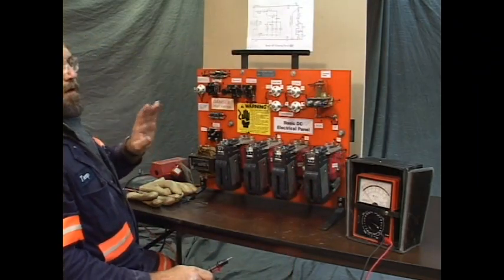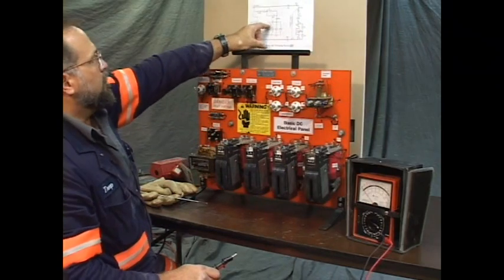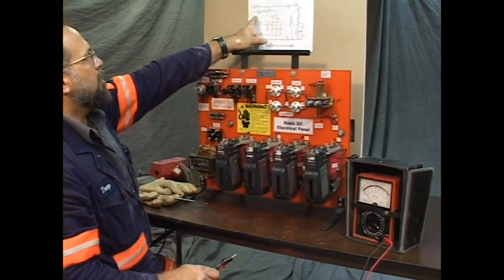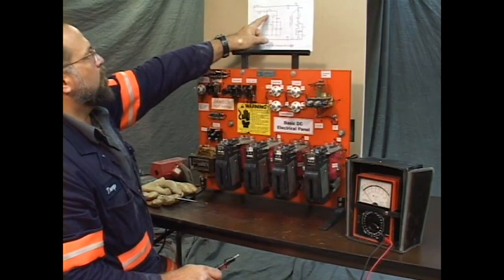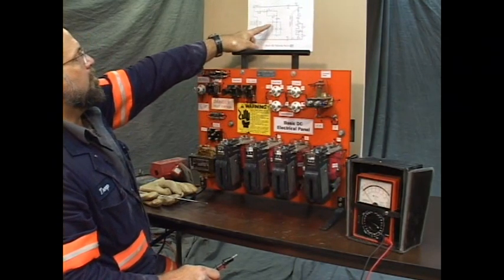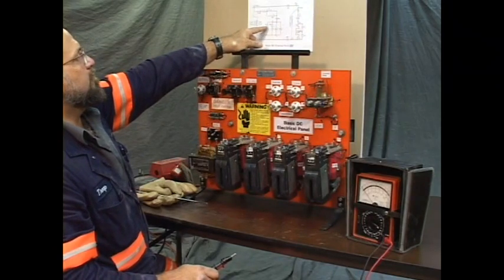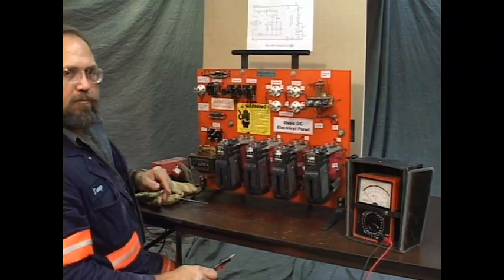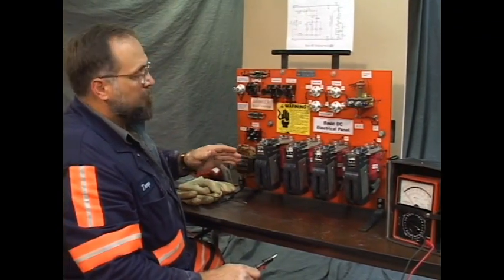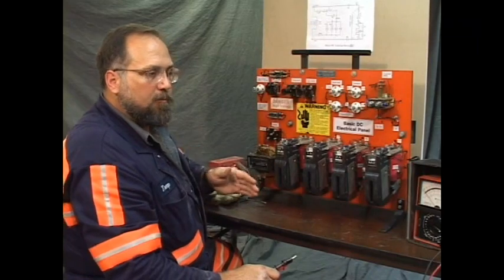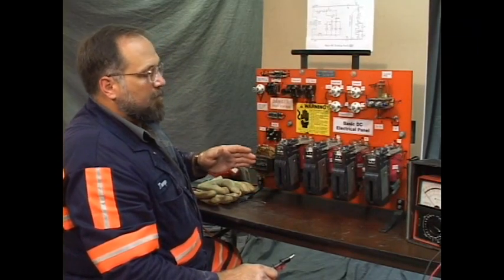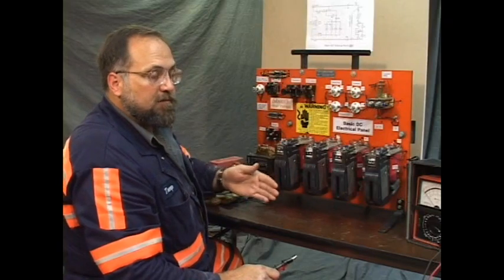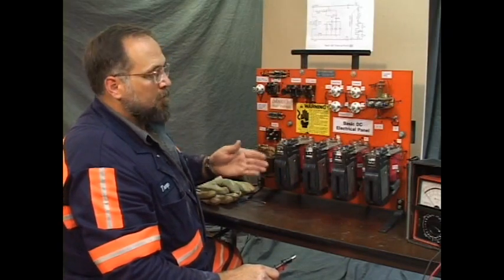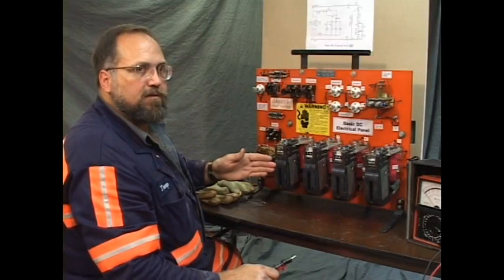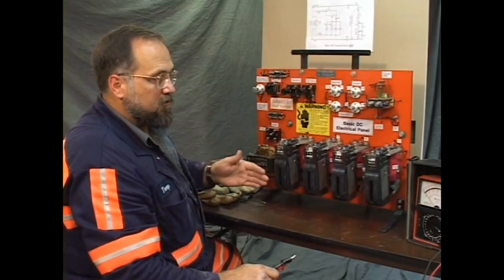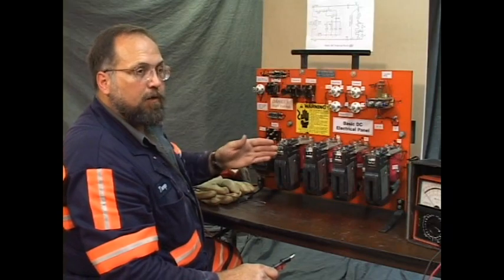Had there been a problem anywhere on that circuit, if you remember the problems that we found, we had an open wire here, we had an open wire here, we had an open wire there, we had a shorted mercury tube, we had a shorted mercury tube. Out of the 15 that we checked, those problems became apparent after we saw the symptom, we read the problem, we saw the panel operate, and through these many minutes and even hours of testing the panel, we could have found any one of those had they existed just now, in just a few minutes, with no power, no hint.